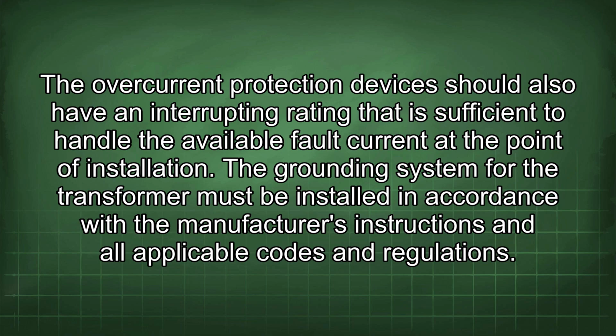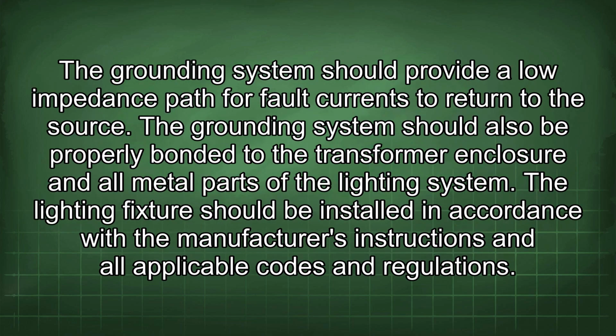the point of installation. The grounding system for the transformer must be installed in accordance with the manufacturer's instructions and all applicable codes and regulations. The grounding system should provide a low impedance path for fault currents to return to the source. The grounding system should also be properly bonded to the transformer enclosure and all metal parts of the lighting system.